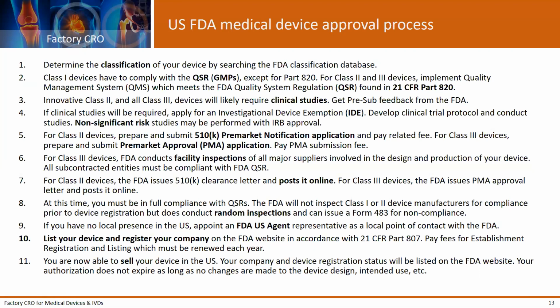However, in Europe, this is a certification system. The FDA does not audit and certify companies for being CFR compliant. This is basically a law and you need to adhere to it. Innovative class 2 and all class 3 devices will likely require clinical studies. If you need to perform clinical studies, you need to apply for an IDE. I will explain more about this later in the presentation.